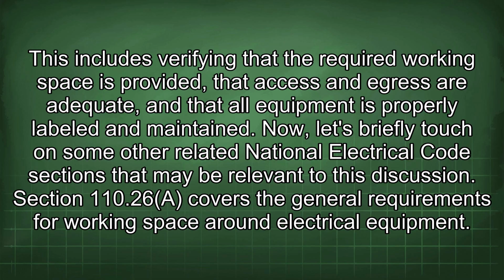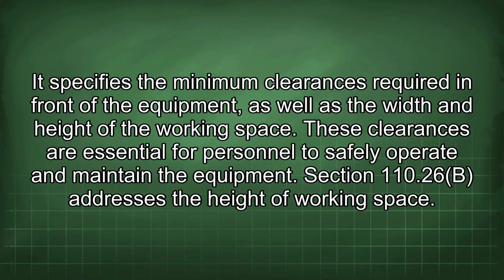This includes verifying that the required working space is provided, that access and egress are adequate, and that all equipment is properly labeled and maintained. Now let's briefly touch on some other related National Electrical Code sections that may be relevant to this discussion. Section 110.26 covers the general requirements for working space around electrical equipment. It specifies the minimum clearances required in front of the equipment, as well as the width and height of the working space. These clearances are essential for personnel to safely operate and maintain the equipment.